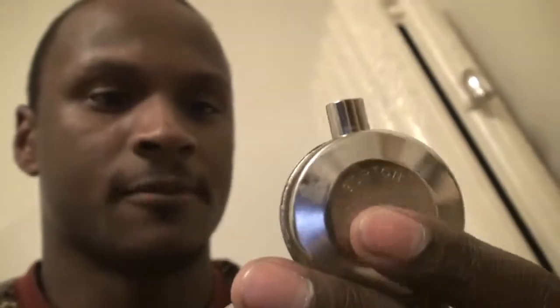You can take a good look at the air valves that I use, which is a Hoffman air valve. These air valves are best known for venting the radiator and getting all the air out, and you can actually hear it running in the background. Another valve that I do use is Gordon's valves. It seems like over the years people have designed plumbing parts to be very cheap. So I'll go for Gordon's or Hoffman, but unfortunately Hoffman are not made the same way they used to be, so now they pretty much seem to break down a lot.